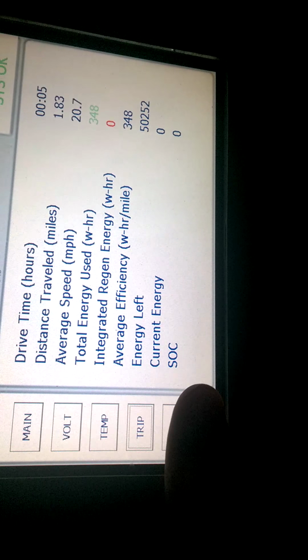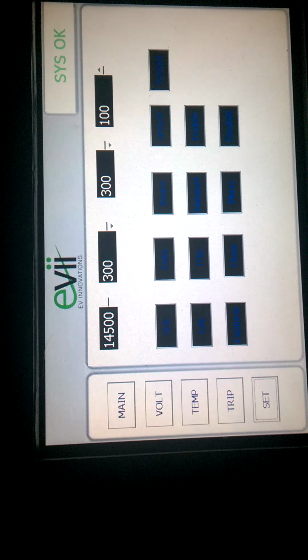Then this last screen is the set, more like the settings. I wouldn't play with it too much because I've got it calibrated now, but if you ever need to do calibrations, you can come to this screen, and right here is a calibrate button. If you know you're right at 0 current in and out, you can push calibrate, and that'll set the 0 point again for you. I'd just use that if you find the values are drifting.